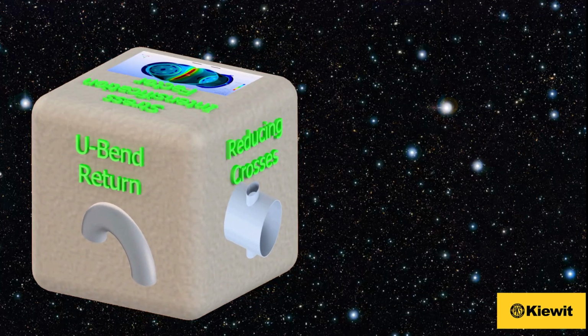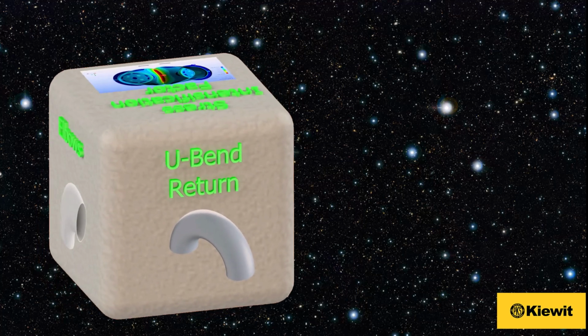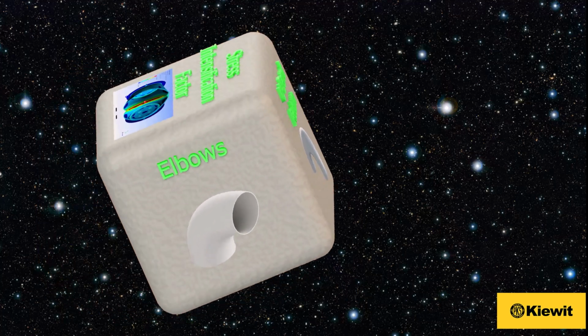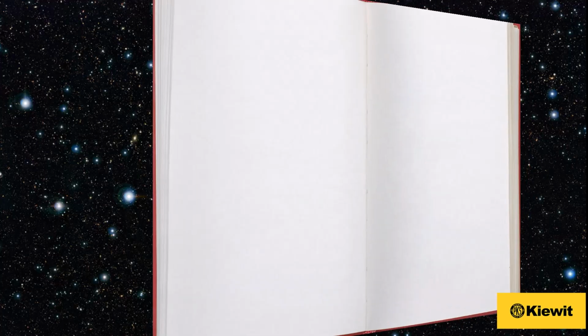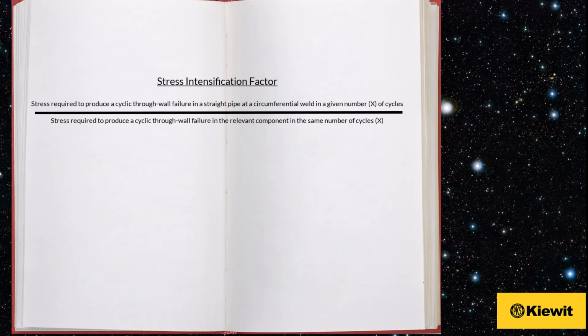So exactly how is a stress intensification factor determined for a given pipe component? Let's look at the definition for stress intensification factors. The stress intensification factor is just simply a stress ratio. It's defined as the stress required to produce a cyclic through-wall failure at a circumferential weld in a straight pipe for a given number of cycles.